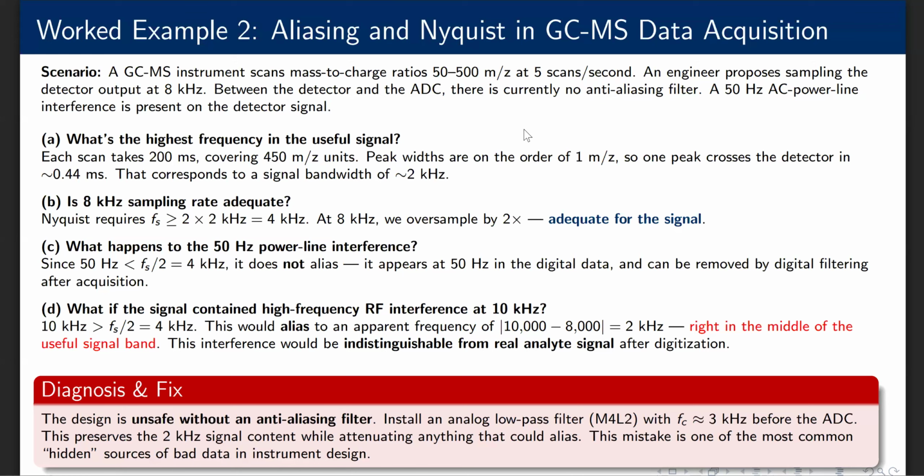So this is important to check. This is a silent failure. The data will look normal, but contains fabricated peaks. And so there's no way to diagnose it from the digital data alone.